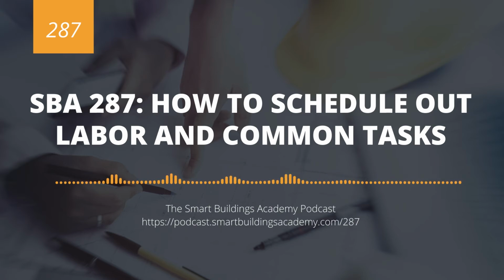So the worst thing, in my opinion, that you can do is go by points, like say, okay, we've got 1,000 points and we're going to have so many hours per point, because points aren't equal. You could have 1,000 VAV box points, and that's pretty simple compared to 100 ultra complex central utility points at a tier 4 data center that has zero tolerance for downtime. That is going to be a totally different level of complexity. So be cognizant of that as you approach things.